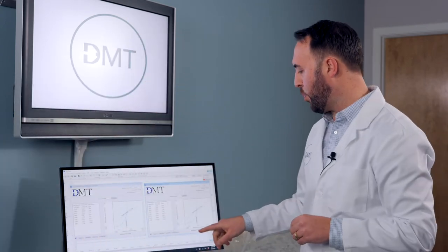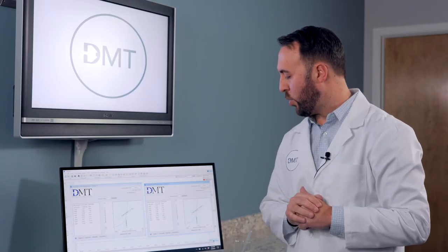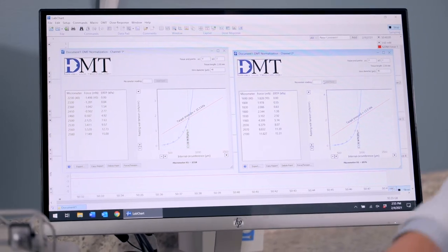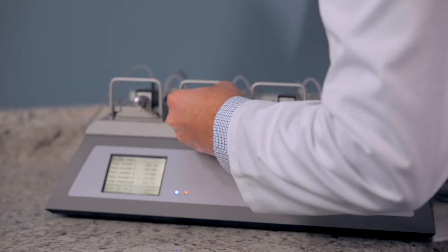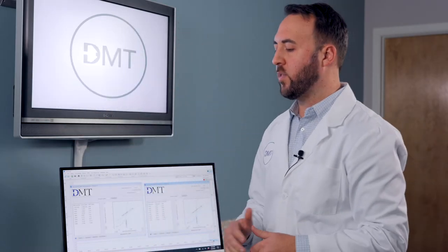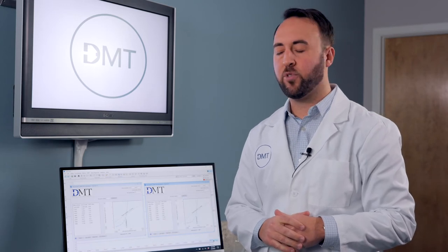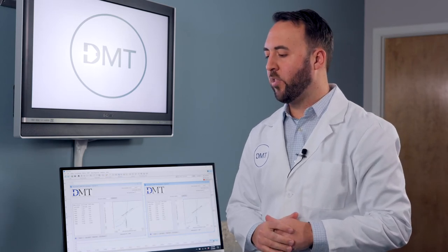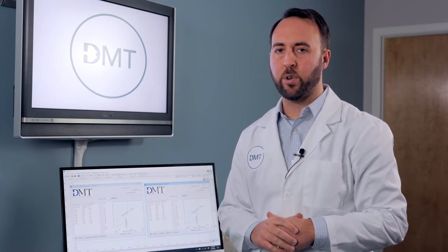And channel 2 has also passed it, and in this case, its reading is set to 2076. So we will move these back to those values. And now that you have done this, you can zero your chambers, your reading for chambers 1 and 2, and this is the point at which you are ready to move on and start the wake-up protocol.